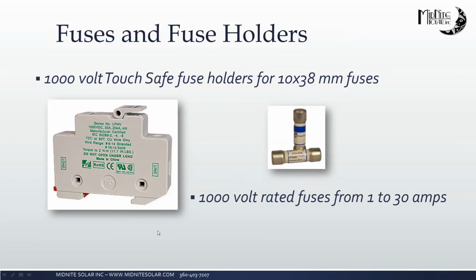Also, we have the option of fuses and fuse holders. So if you need to go above the rating of our circuit breakers, the 1000 volt touch safe fuse holders designed for the 10 by 38 millimeter fuses are a perfect solution for you. They also fit in our combiner boxes that are DIN rail mount, and those range from 1 to 30 amps.